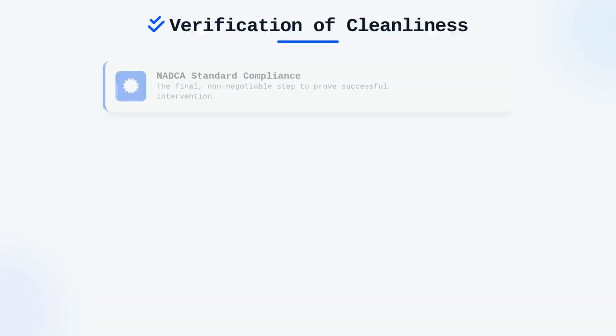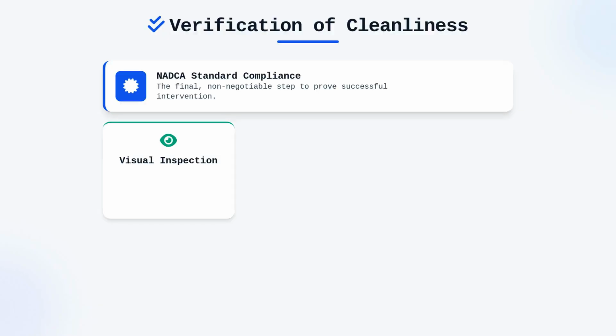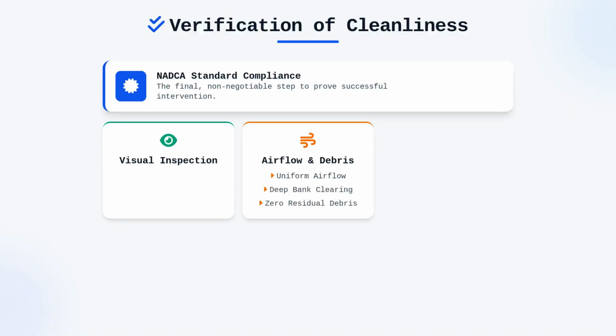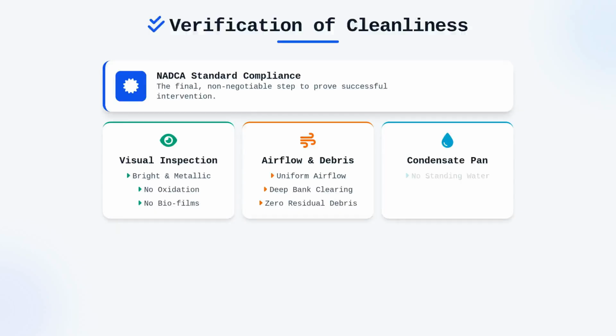Verification of cleanliness is the final, non-negotiable step in the process, mandated by NADCA standards to prove that your intervention was successful. You should evaluate the coils not just by visual inspection, but by checking for uniform airflow and the absence of debris deep within the banks. A clean coil should look bright and metallic without evidence of oxidation or biological films, and the condensate pan should be free of standing water or organic slime layers.